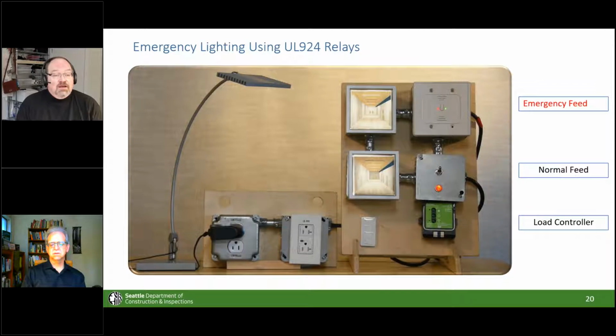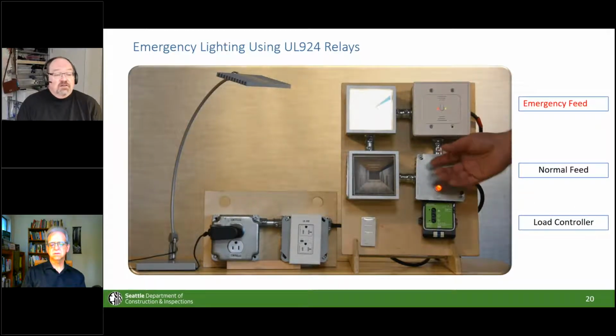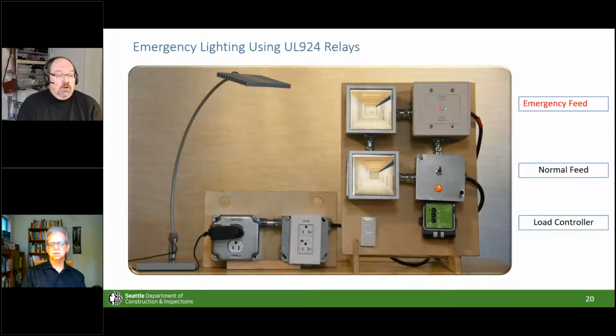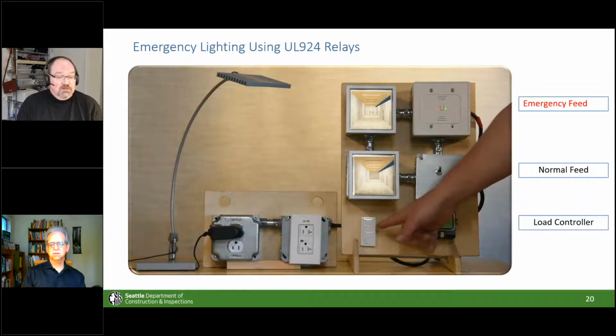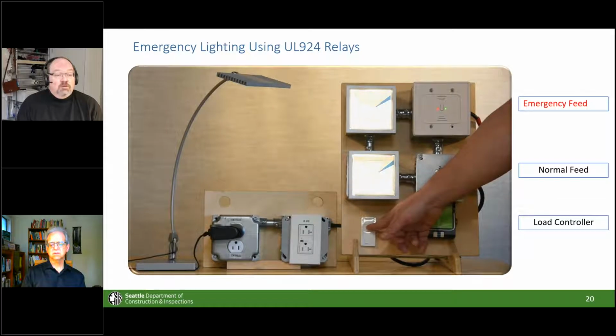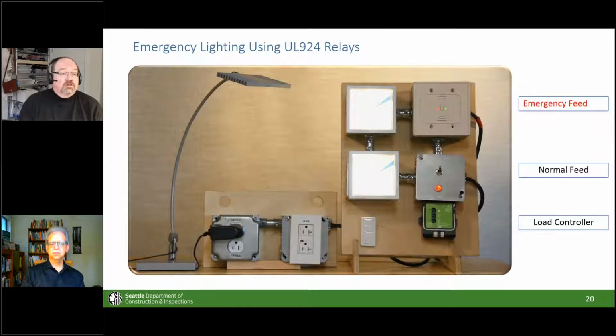Because we have the 924 device on top with its emergency feed, as soon as I lose the normal feed, the emergency lights on top immediately go to full output. Once normal feed is restored in this system, you go back to the level you had before, and you regain the ability to dim up and down. So this is one relatively easy way to make sure we have the ability to control the emergency or egress lights from this kind of system.